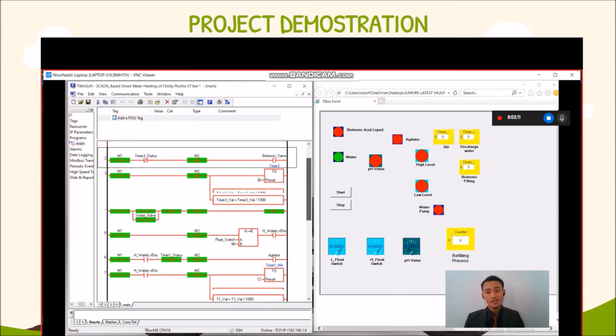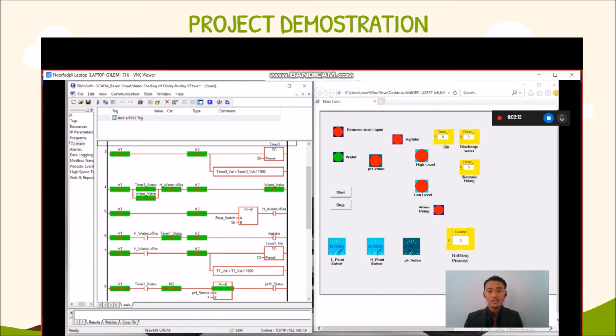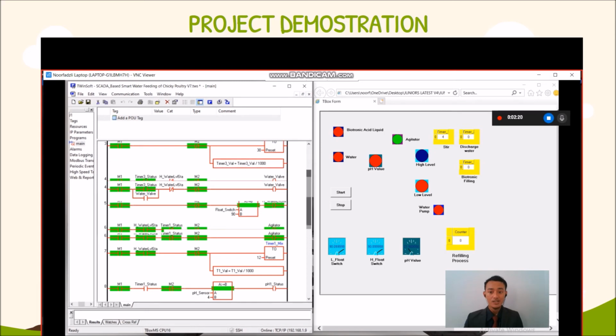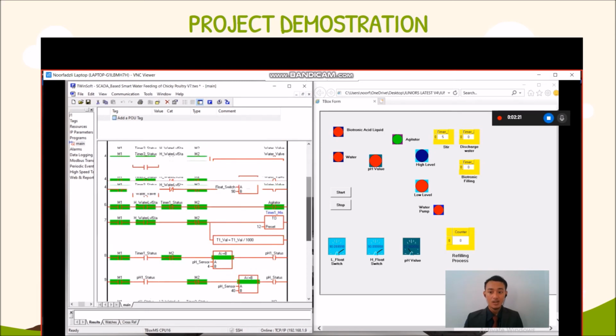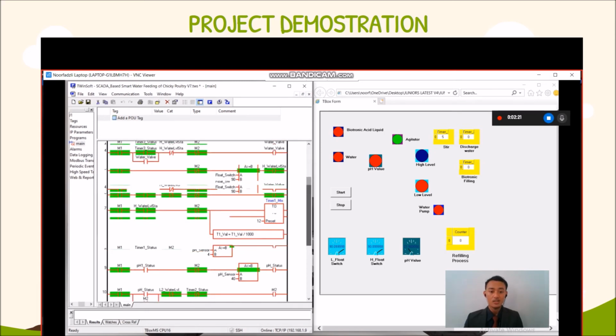Then the comparator will compare if the float switch sensor is equal to 90. If the condition is met, then the high water level is triggered. Then the high water level status will trigger the agitator. The agitator will stir the biotronic acid liquid and water blend together for 12 seconds. Then timer 1 for stir is counting up to 12 seconds.